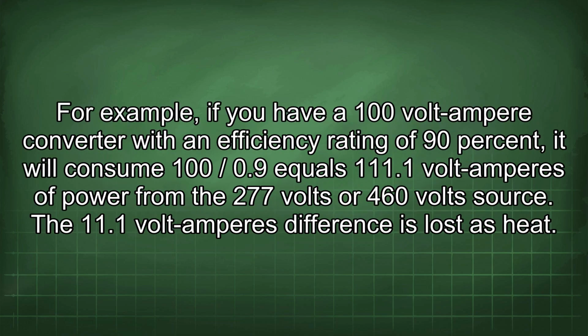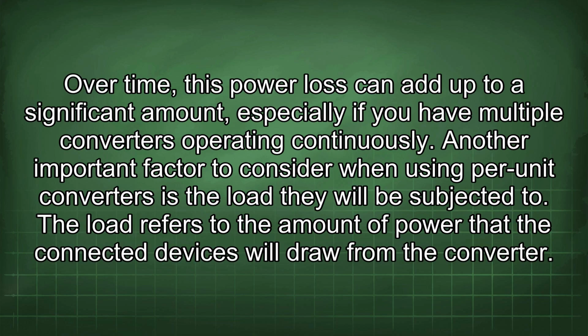For example, if you have a 100 volt ampere converter with an efficiency rating of 90%, it will consume 100/0.9 equals 111.1 volt amperes of power from the 277 volt or 460 volt source. The 11.1 volt amperes difference is lost as heat. Over time, this power loss can add up to a significant amount, especially if you have multiple converters operating continuously.